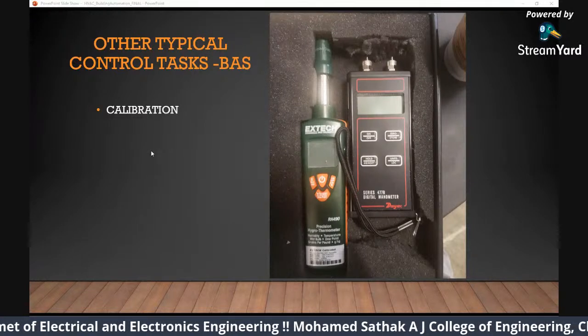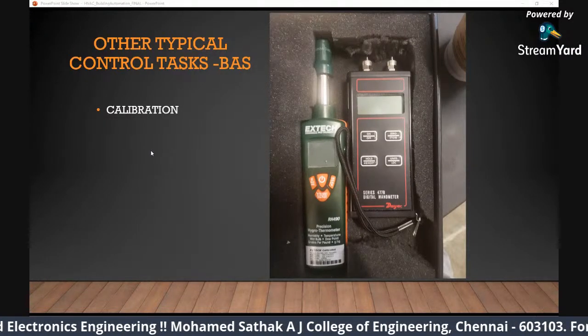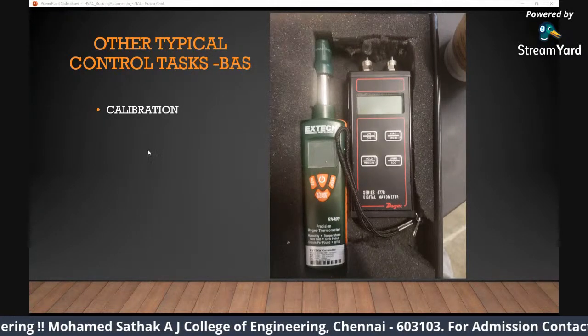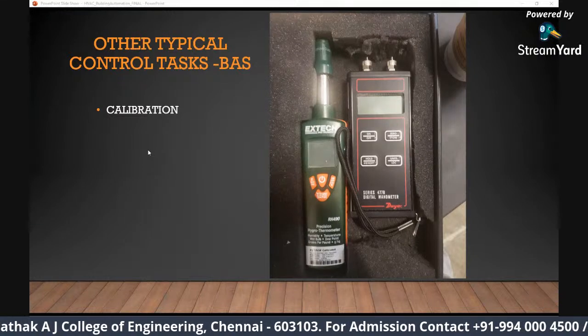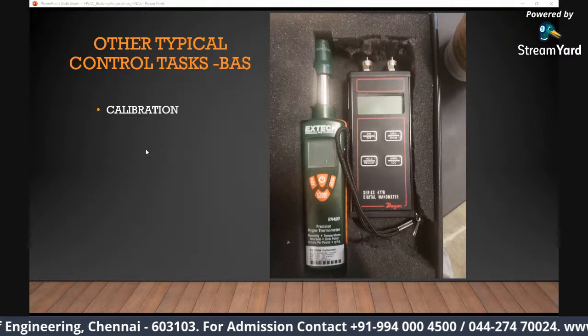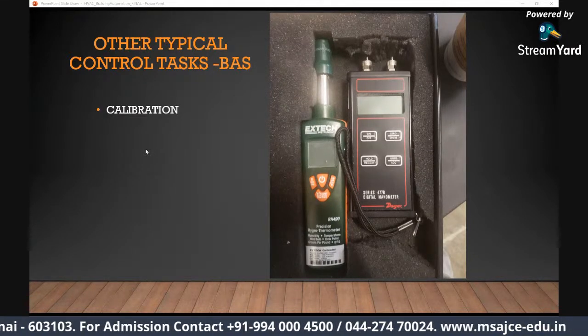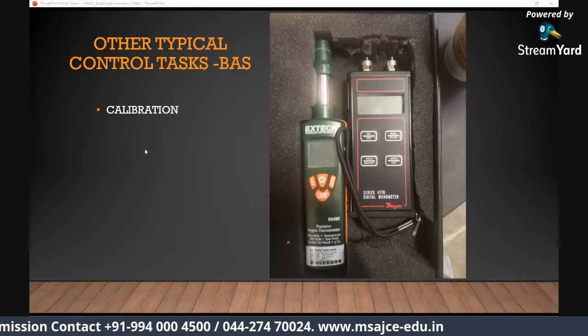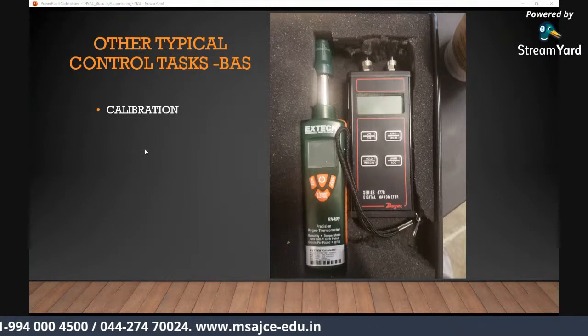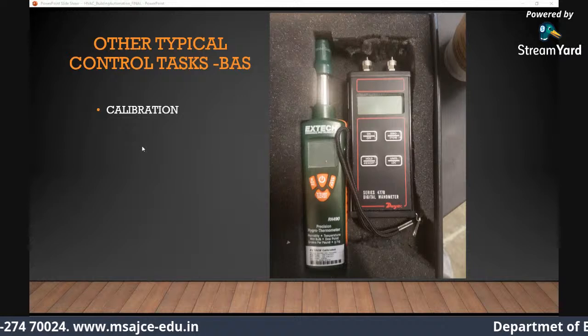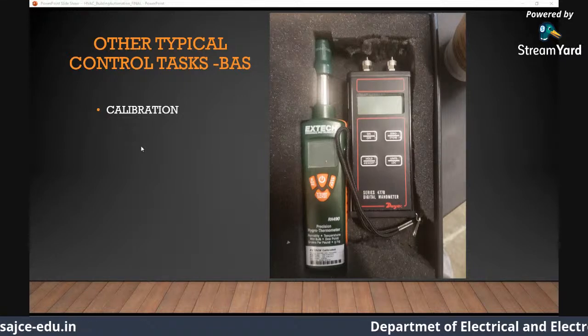Apart from that, we do different aspects in building automation, calibration. Let's say a control sensor is not reading. Let's say the temperature is actually 23 degrees Celsius, but it is measuring 25. So we have to go and measure it, adjust it accordingly to make it read good. That we call calibration in the instrumentation industry. We have to calibrate each and every individual sensor.